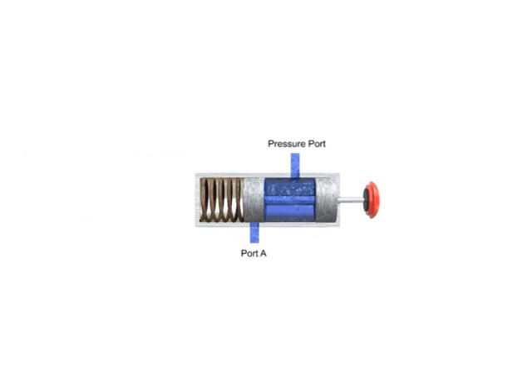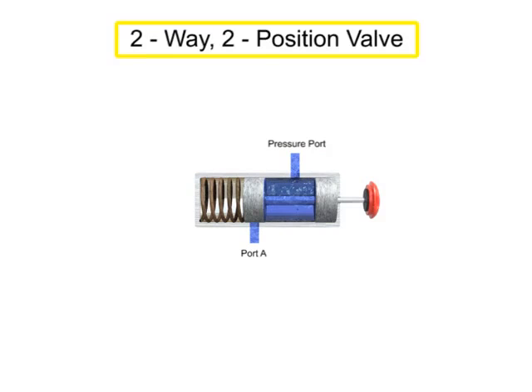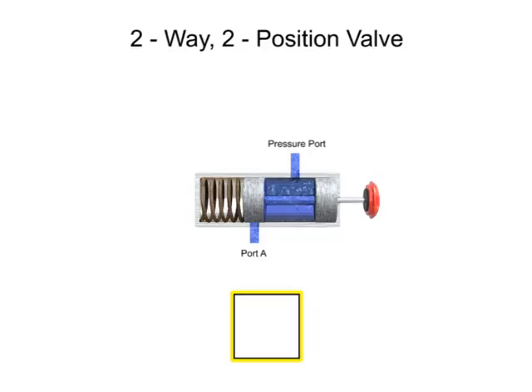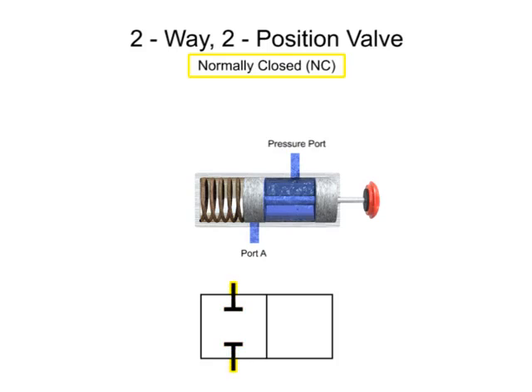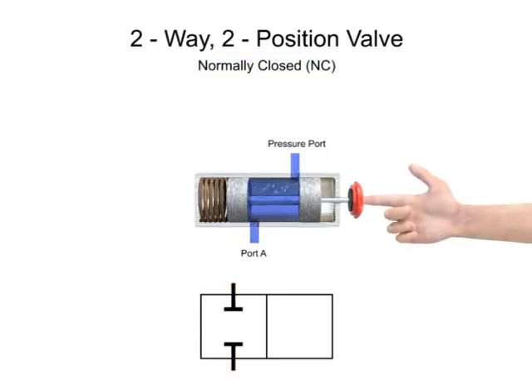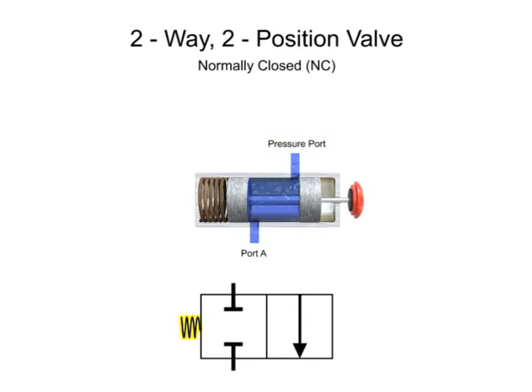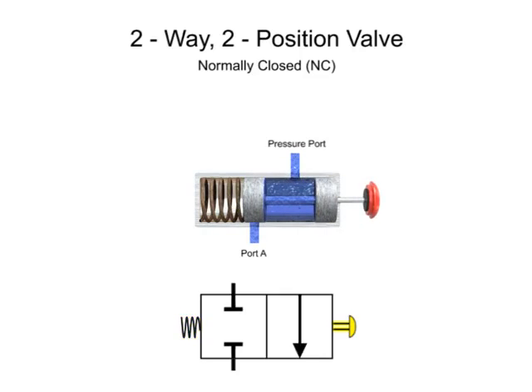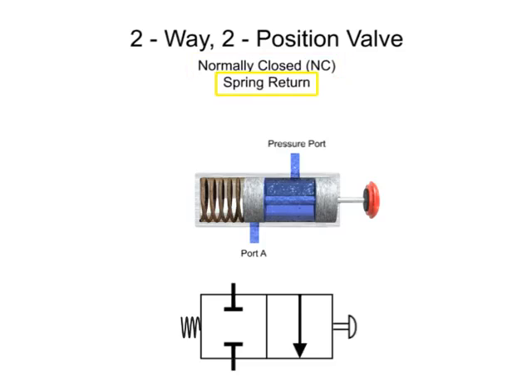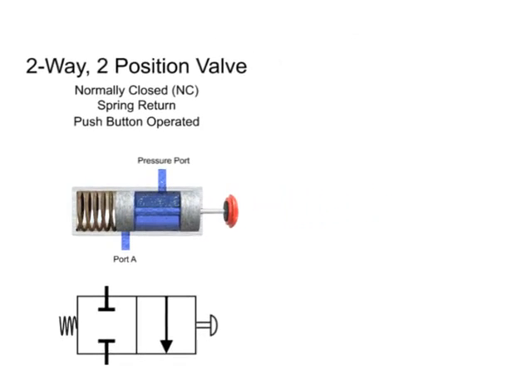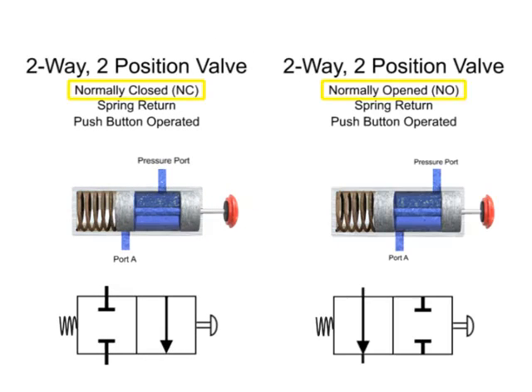Here is a similar valve to the one previously shown. It has two ports and two positions, so it is also a two-way, two-position valve. However, in the normal non-actuated position, both ports are blocked. Therefore, it is a normally closed valve. When the valve is actuated, fluid is allowed to flow from the pressure port to port A. A spring returns the valve to its normally closed position, and a push button actuates it to the open position. Therefore, this valve is a two-way, two-position, normally closed, spring return, push button operated valve. While it is similar to the previous example, the differences in the normal position make it a distinctly different valve.